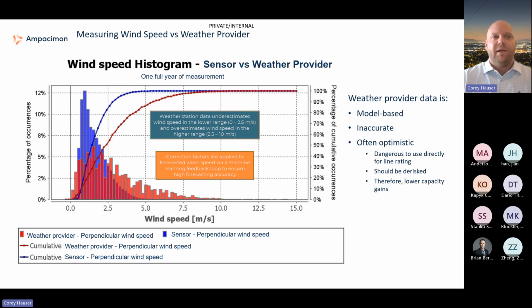So on the low end, as you can see noted there in the middle as well, so I'd call it 2.5 meters per second or so or less, the wind speeds are underestimated, so you're not capitalizing on those gains. However, even more scary and dangerous is that once you get past that point, they're overestimated. And as you can see here, even when you get to areas such as 5 meters per second and above, up to 10, there are times where the sensor isn't reading anything, but the weather provider is providing a 5, 7.5, 10 meter wind speed value, which is the part where, yes, your ratings are going to be incredible, but they're not correct.